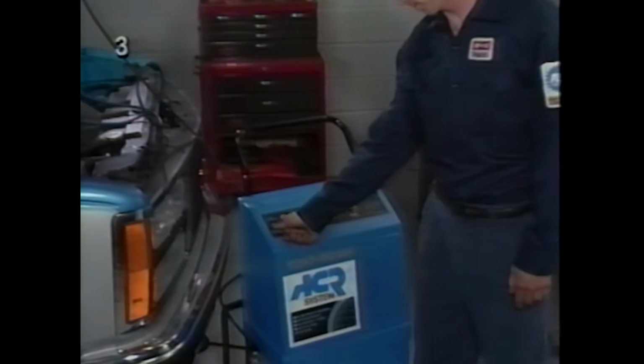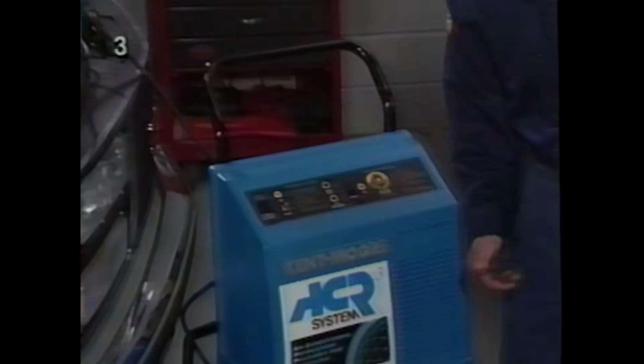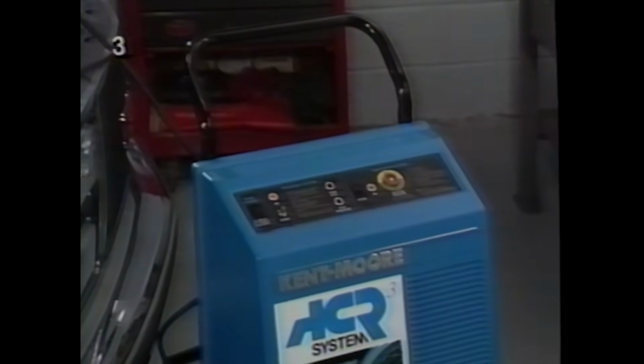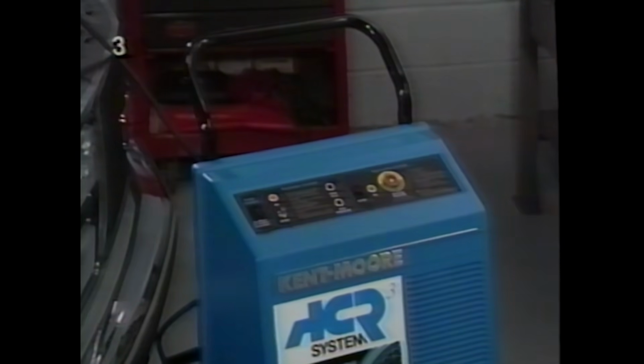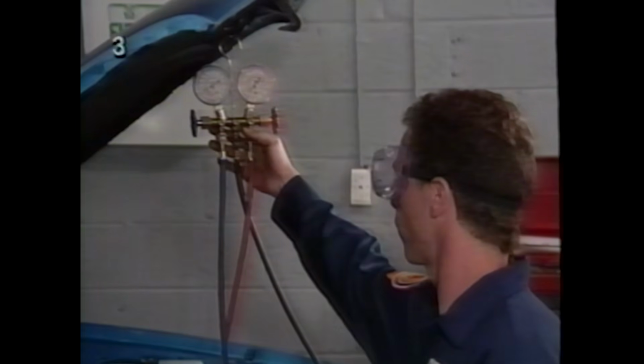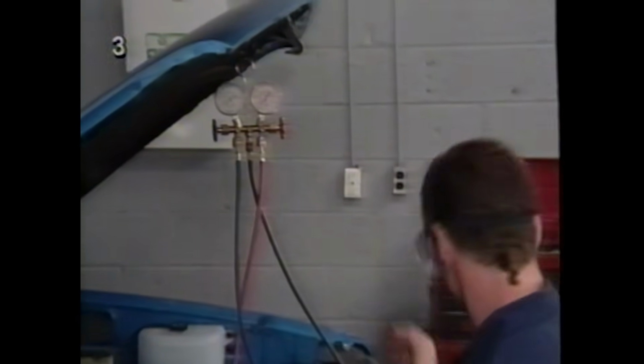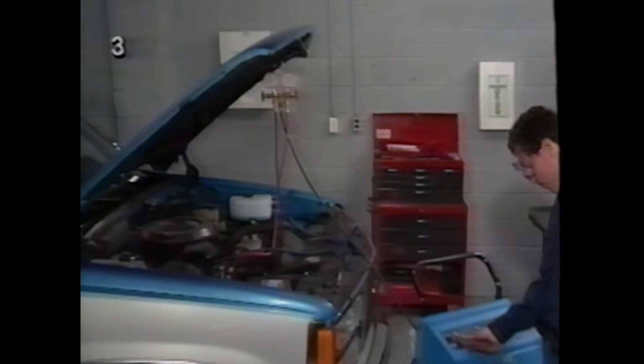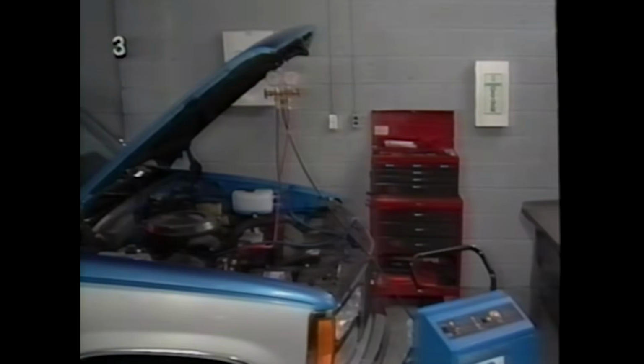Plug in the ACR3, turn the power on and push the compressor start switch. It should turn off by itself when the recovery operation is finished. Check for an increase in pressure after 2 minutes. Then push the switch to start the compressor again and repeat the recovery operation.